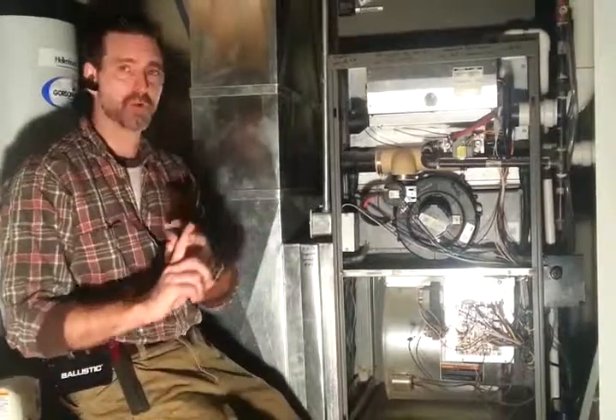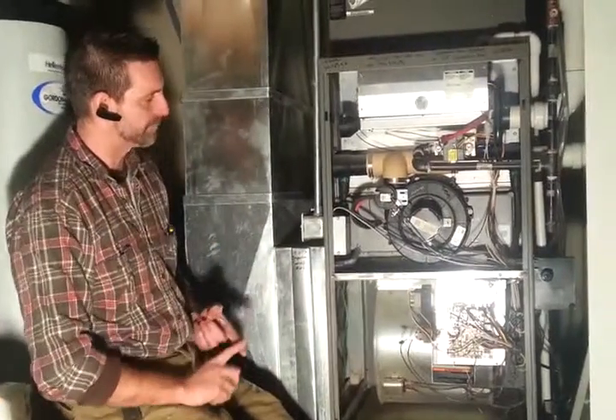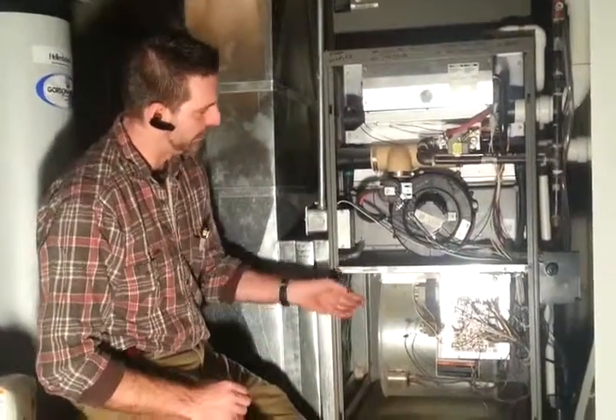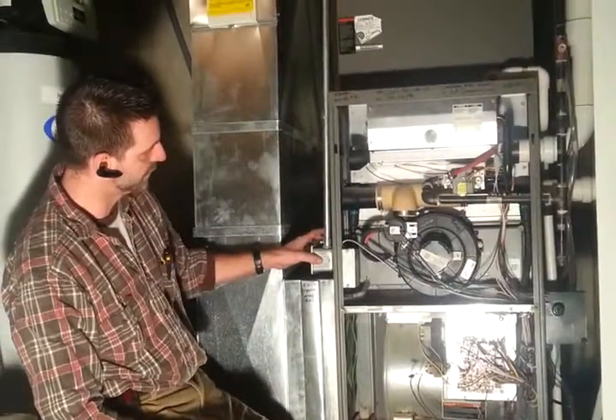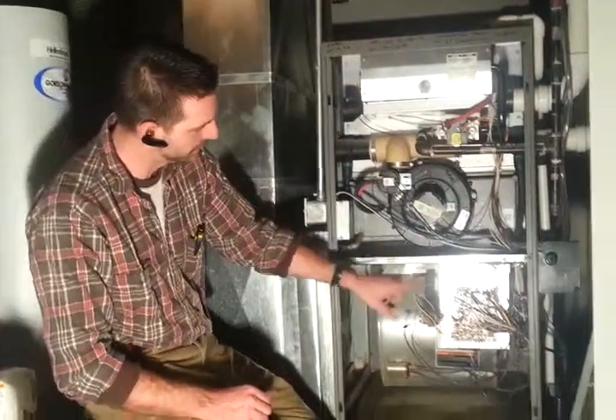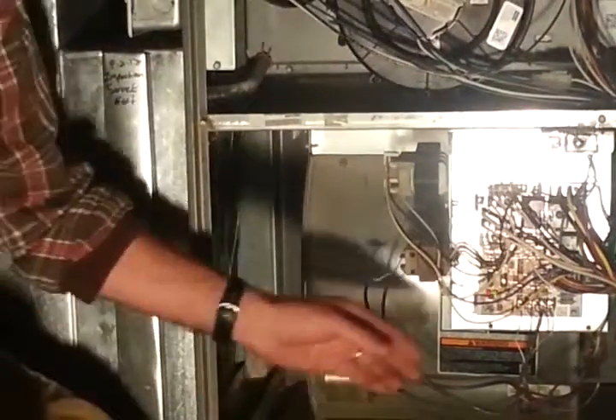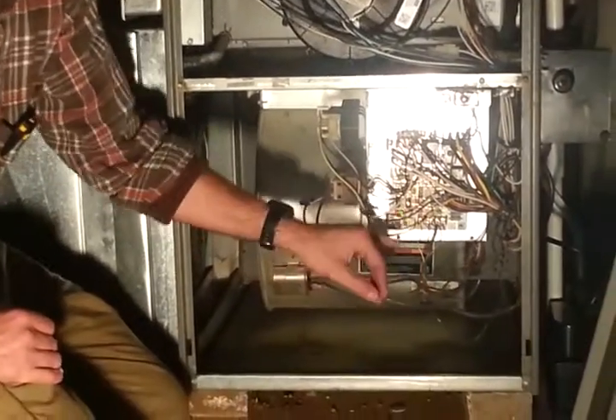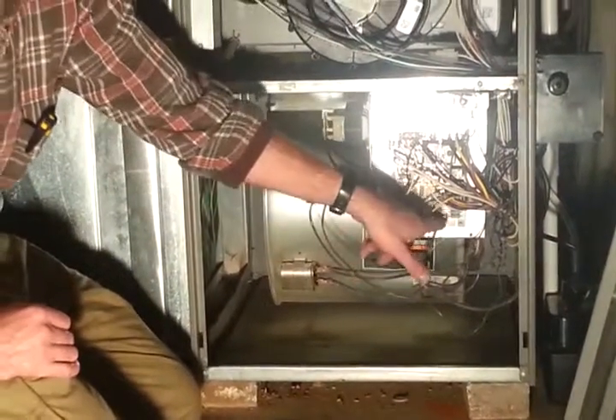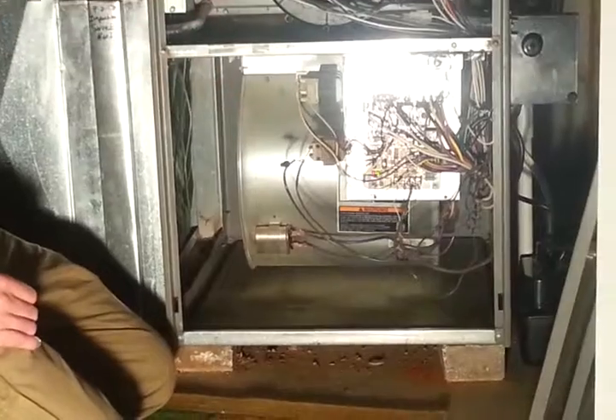So let's talk about the order of the operation. The first thing that happens is, of course, we get 120 volts that comes in here. Here's my power switch. It comes into my transformer. This transformer's job is to convert that 120 down to 24 volts. We take that 24 volts and we take it up to our thermostat on the red wire. And there's an R labeled here. That goes up to your thermostat.